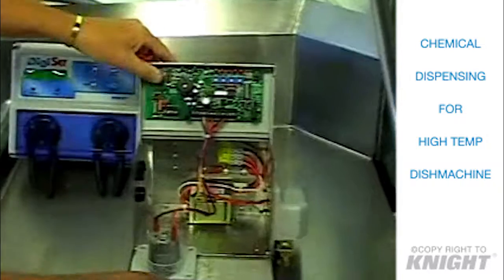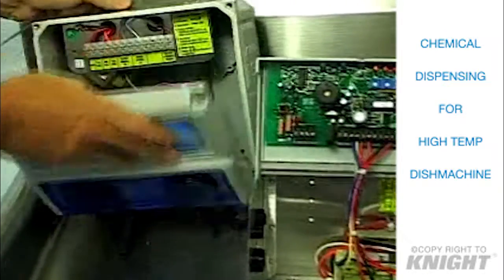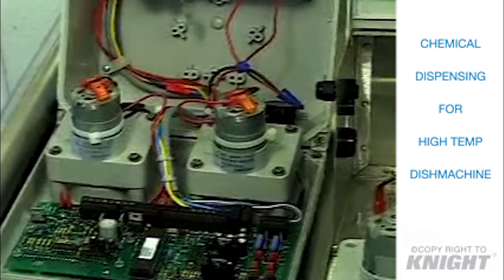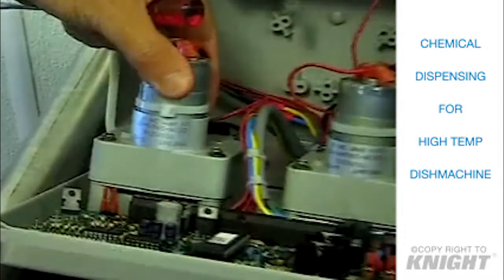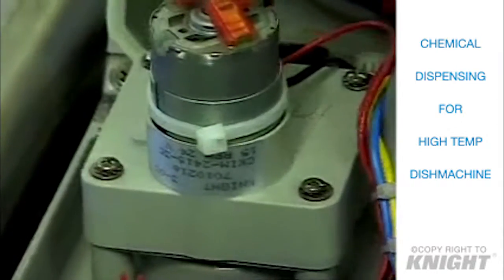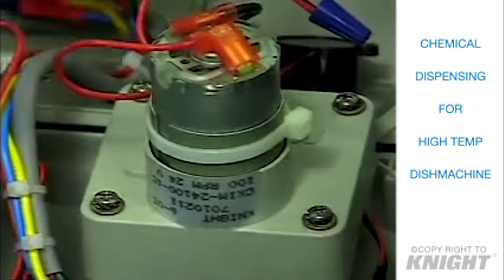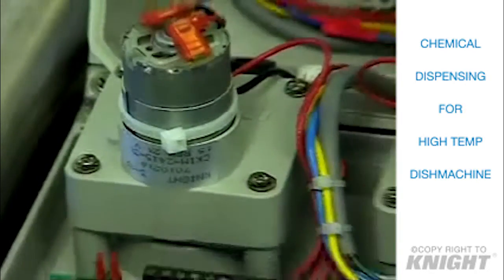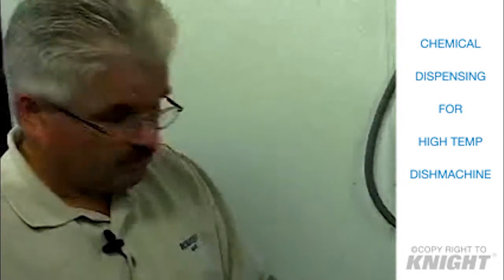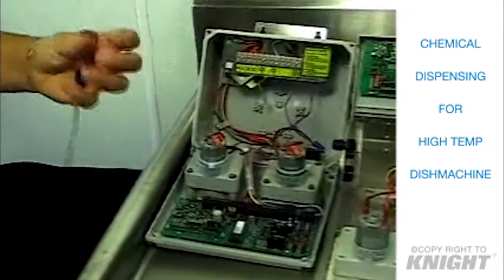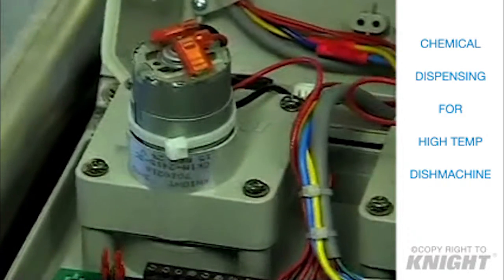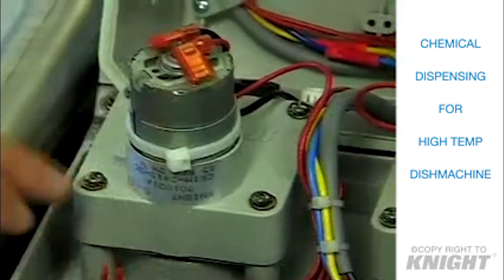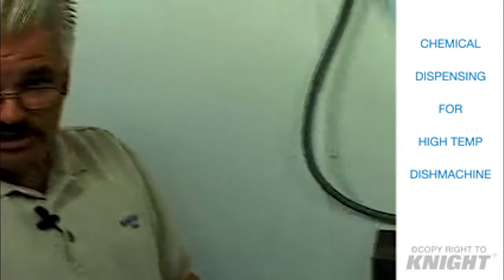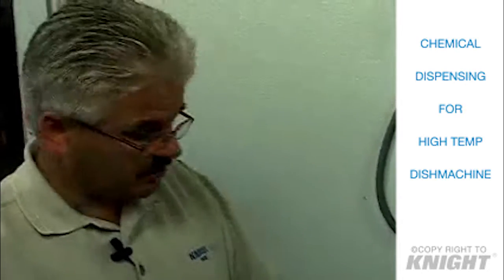If we open up these dispensers and look inside, you can see also that there's two different pumps. One, the rinse pump, which on this one is a 15 RPM pump, and the detergent pump is a 100 RPM pump. The reason they're different speeds is because detergent we want to get in quickly, so that we add the detergent quickly to the concentration of the wash tank so we get the full use of the wash with full concentration of detergent. But the rinse needs to go in systematically, so it's added to the rinse water as sparingly as possible to get the best results. So you also will need to have at some point a replacement motor, because these are DC motors, and although our motors last for a very long time, they will eventually wear out and need to be replaced.